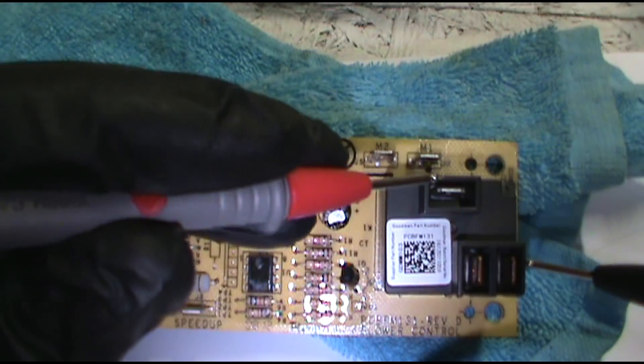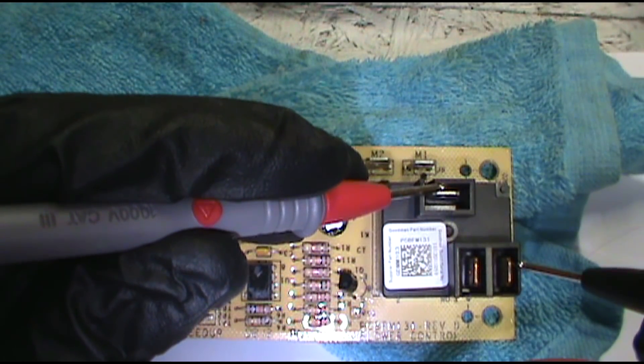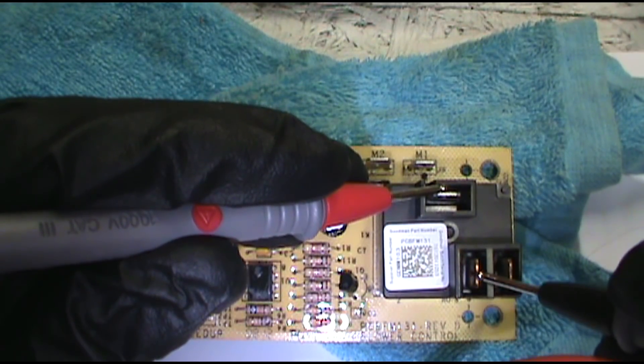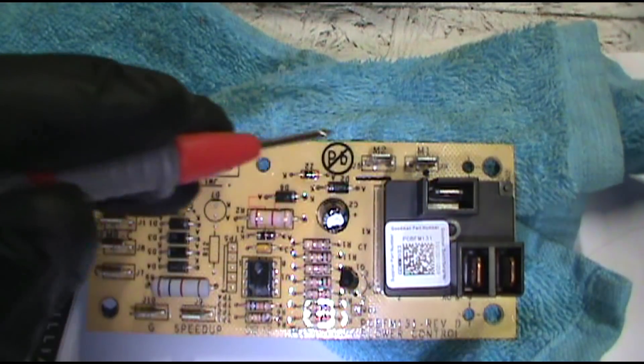And if it beeps, that means the switch is welded shut and you're going to need to replace the board. So you can touch normally closed and common. If it beeps, so if you touch this one and it beeps, you need to replace the board because it's welded shut and not turning off.